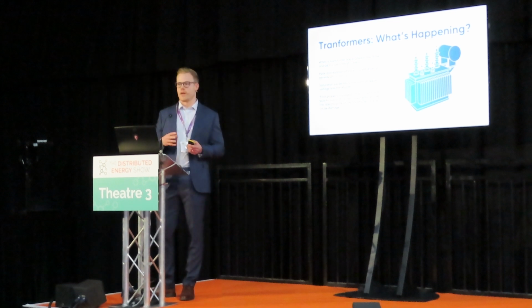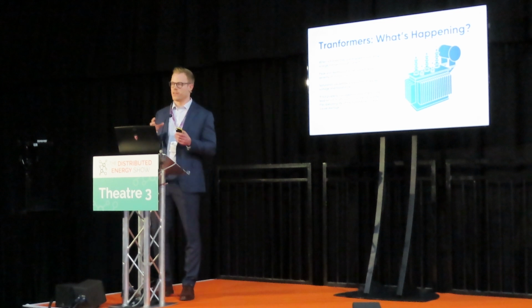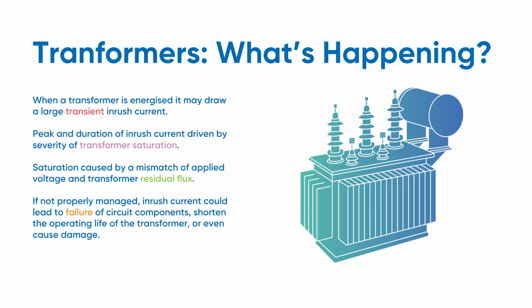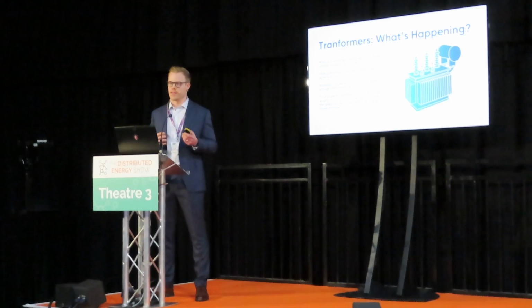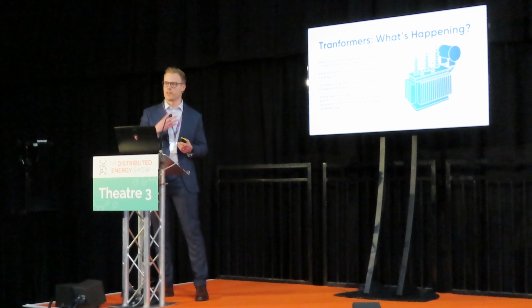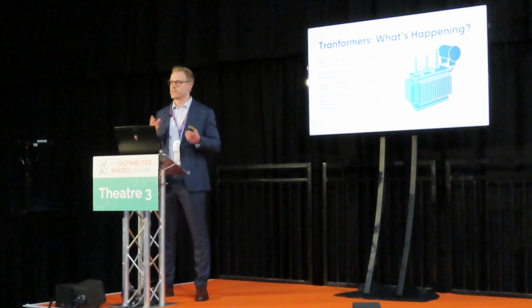Now, there's a phenomenon known as inrush current. If you have a transformer sitting there off and you turn it on, and you cause the transformer core to go into what we call saturation, the transformer will draw a very large amount of current for a very short amount of time. It'll have a very big peak. This inrush current will cause the grid voltage to collapse. And in the UK, we have standards and regulations to say how much you can collapse the grid. That's because it leads to things like lights flickering, disturbance on other people's loads, and general instability in the grid.